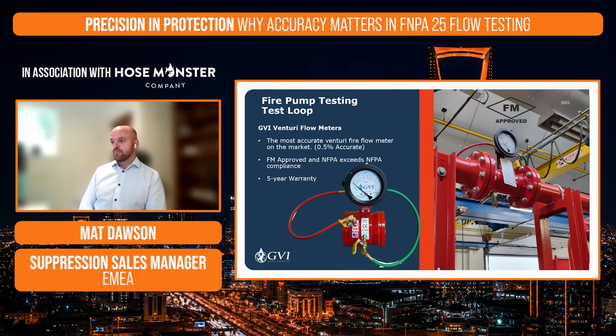So Patrick mentioned GVI, but GVI is our static flow meter range. So whereas Hose Monster's portable, GVI is static, and we install these on test loops. So the difference would be if we were testing a fire pump using Hose Monster, we would flow water out of the test header externally and discharge that water. With GVI, we're using an internal test loop and we're not discharging that water. It's staying within the system.